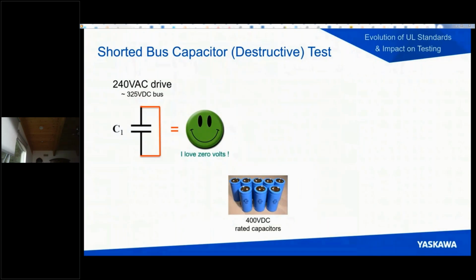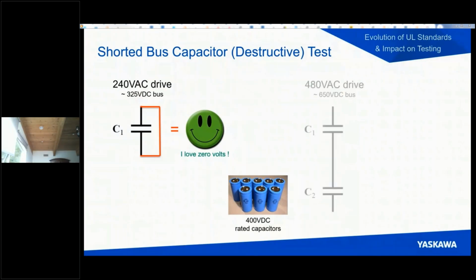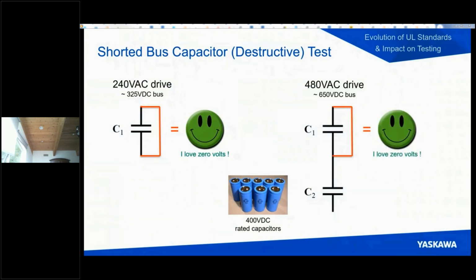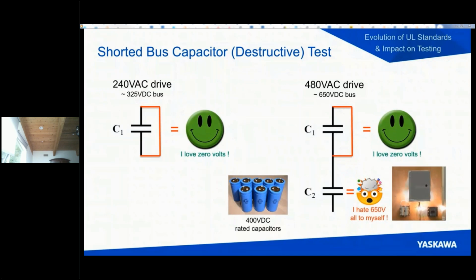But let's look at a 480 volt drive, and this would be similar to a 600 volt drive too. Now keep in mind that the 480 volt drive is using those same 400 volt capacitors, but in series. So normally it would be sharing the voltage. So when we short one of the capacitors, and this is what we're required to do by UL, put a short across one of the capacitors, again, that particular capacitor is very happy. Okay, but the capacitor that's connected in series to it doesn't like it at all, and the result is severe. Right? So again, 400 volt rated capacitors, you're applying 650 volts nominal typical DC to that capacitor, and it doesn't survive, and the event is severe.